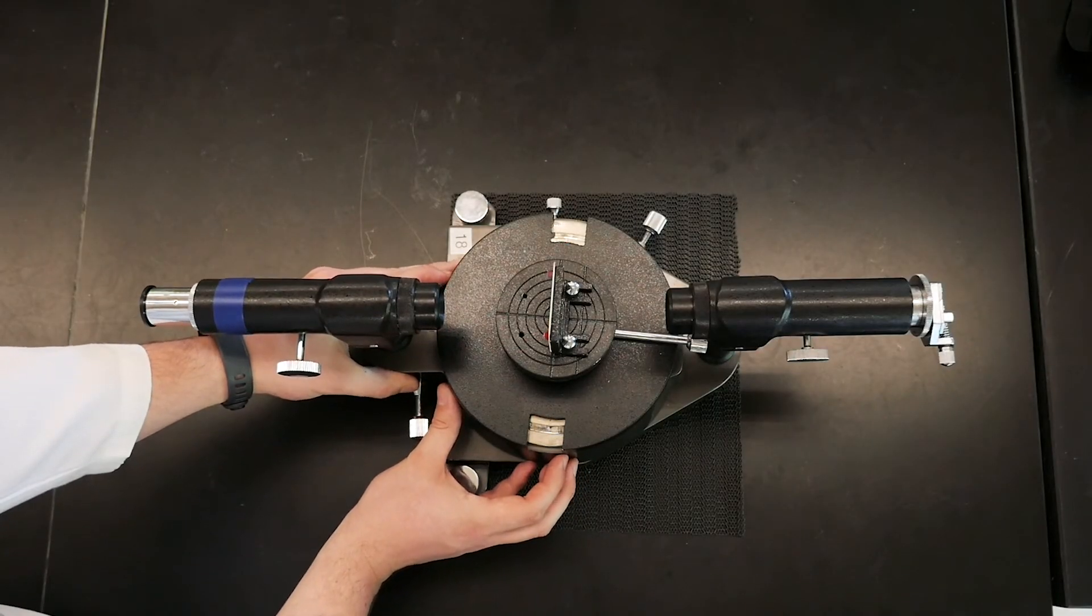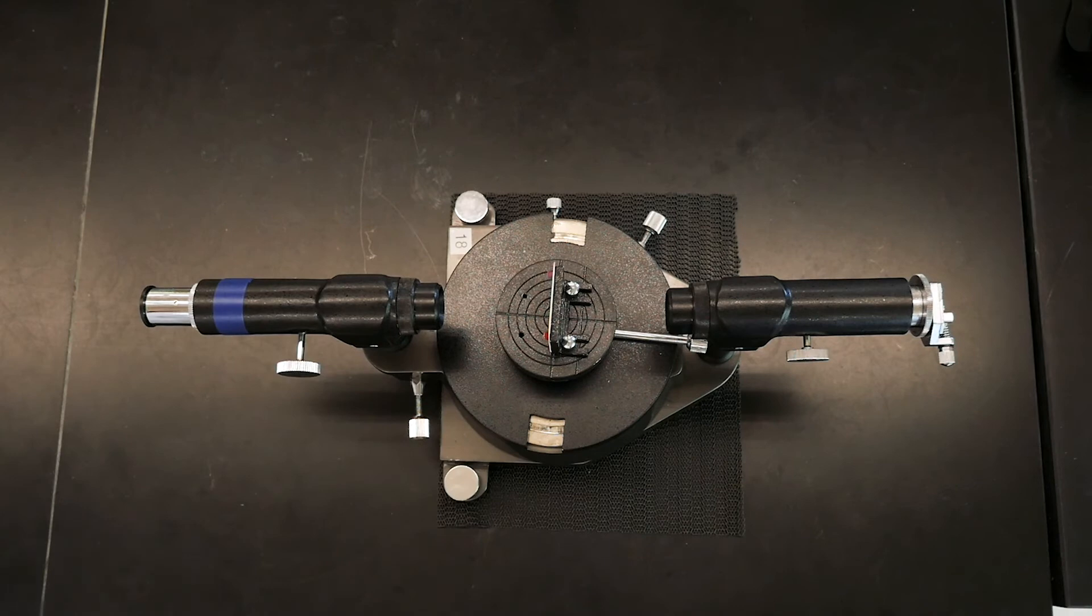Alright, now that the instrument is aligned, we'll need to make sure it's calibrated properly. That's because the amount of diffraction not only depends on the wavelength of light, but also the diffraction grating itself.